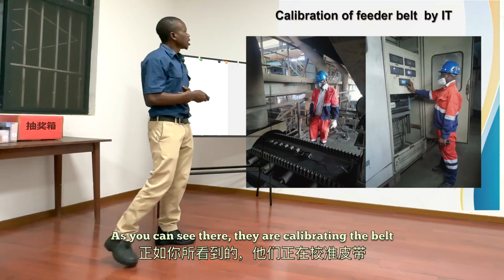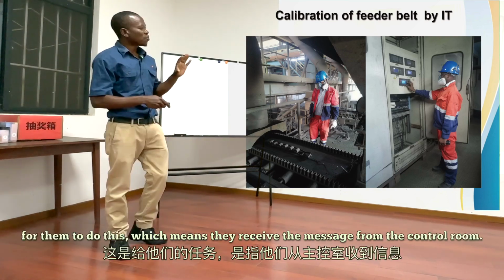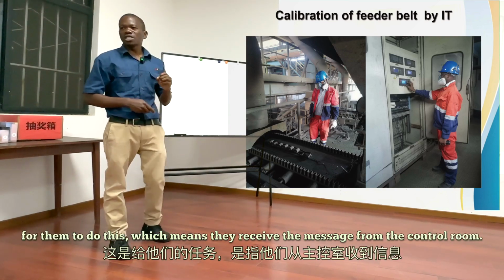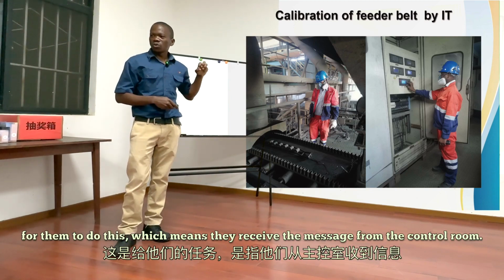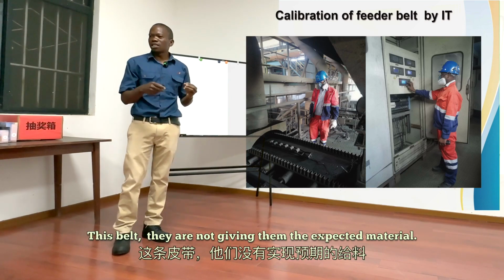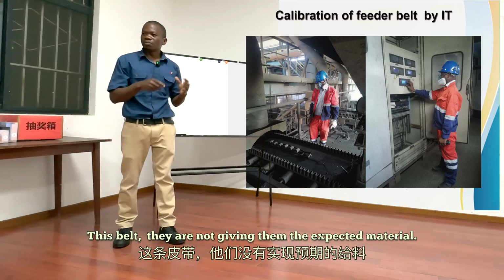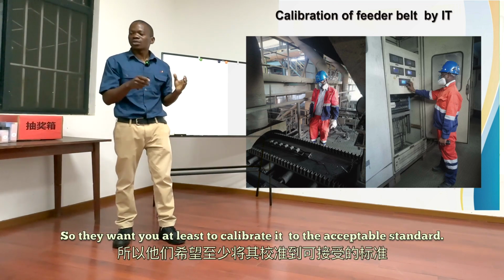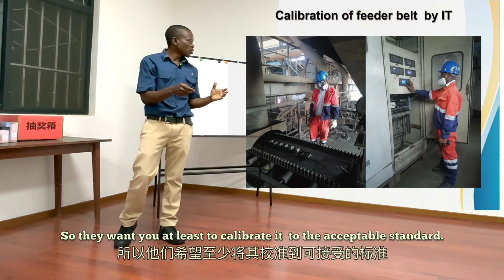As you can see there, they are calibrating the belt. For them to do this, it means they received a message from the control room. This belt is not giving the expected material, so they want you at least to calibrate it to the acceptable standard.